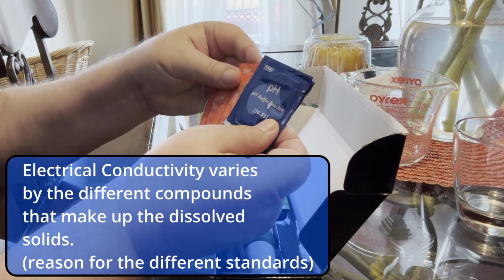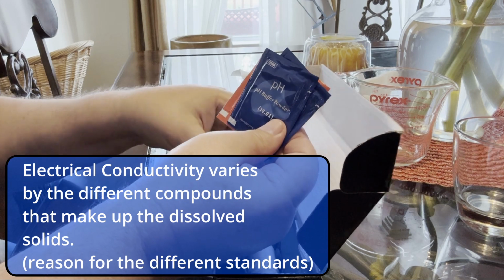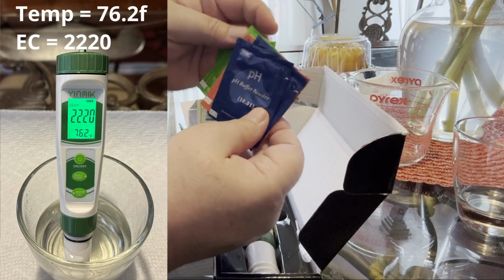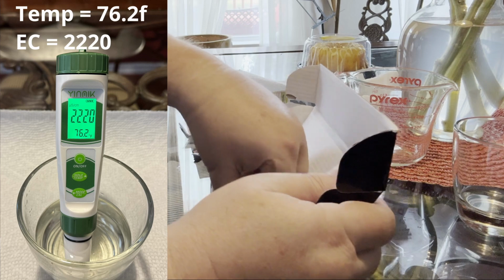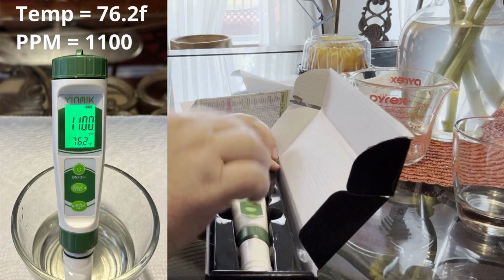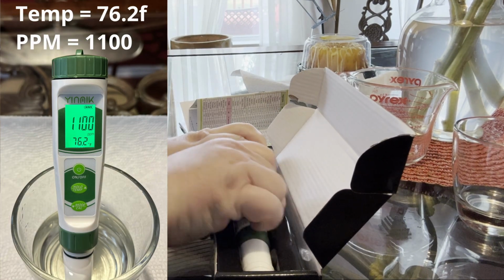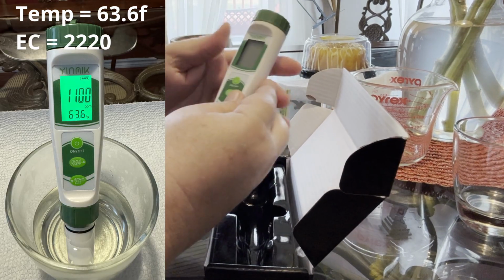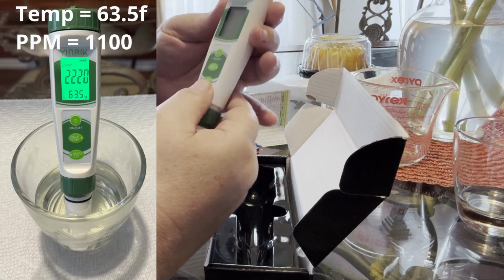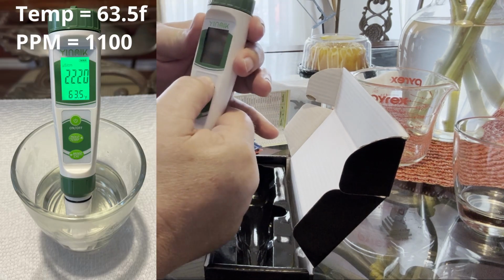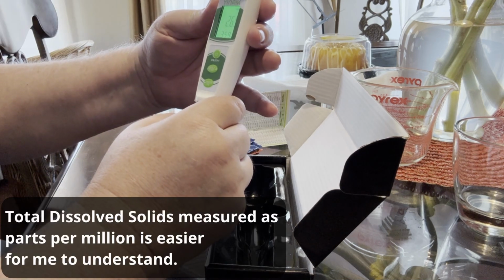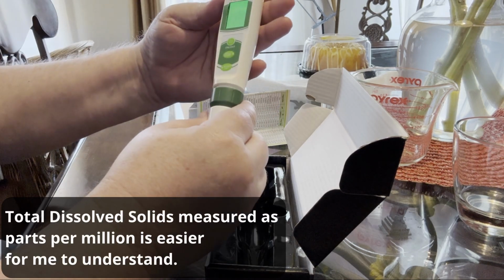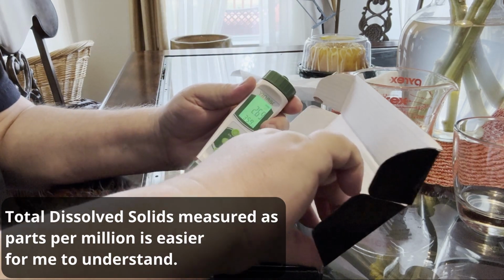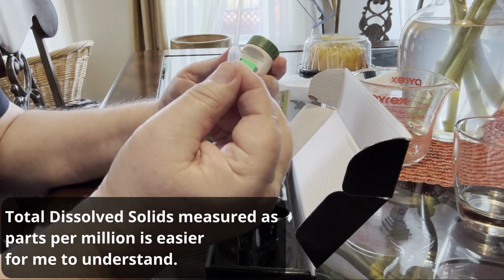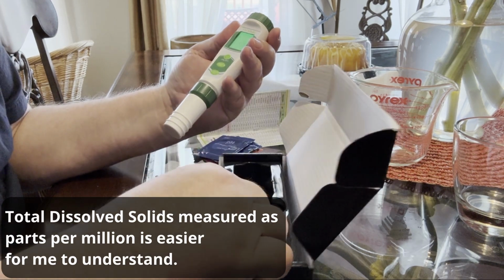However, more significantly, the EC measurement will vary greatly depending on water temperature. The warmer water temperature will show a higher EC reading if your meter is not temperature compensated. The water temperature can change the EC reading as much as 100%. This meter compensates for the temperature in the EC, pH, and ppm conversion. This is why I use ppm when measuring nutrients. This may be slightly controversial as some people online only use the EC reading. I invite you to also listen to their reasoning and make your own decision.